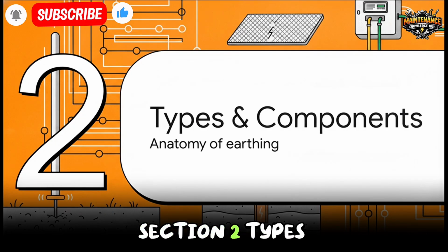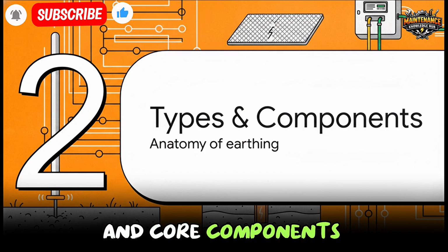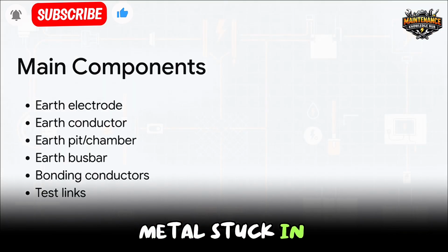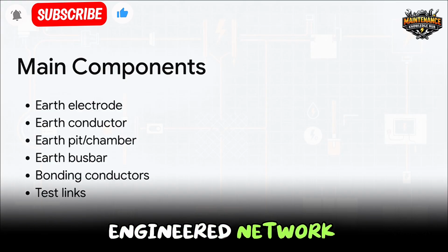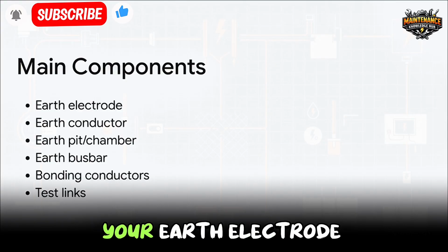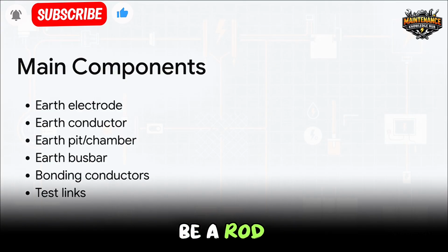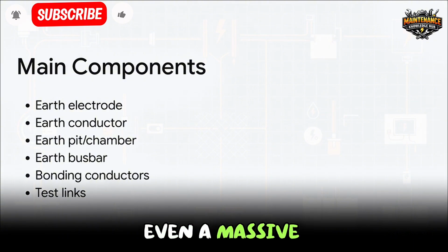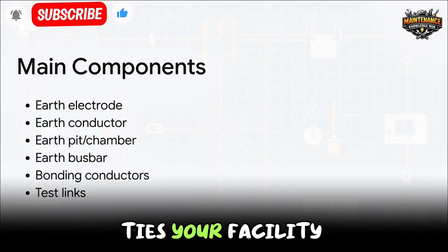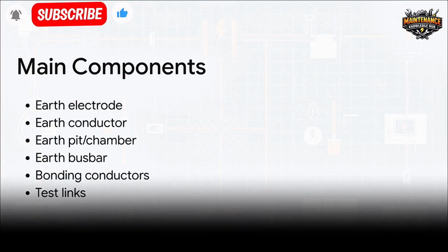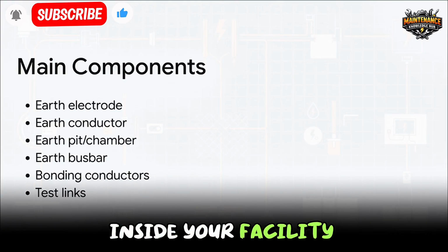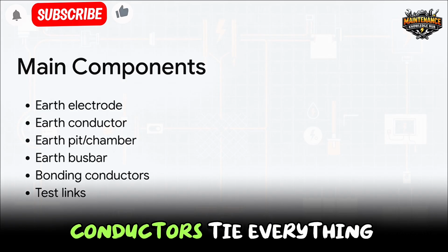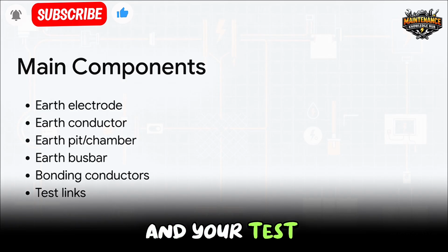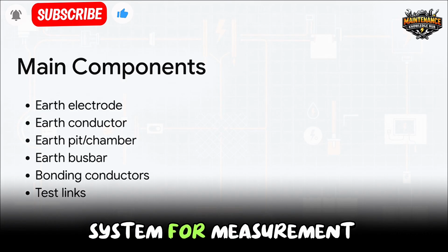Moving on to Section 2, types and core components. This isn't just a piece of metal stuck in the mud. It's a whole engineered network. Deep down in the soil is your earth electrode. And that can be a rod, a plate, a strip, or even a massive mat. The earth conductor ties your facility directly to that electrode, while the earth pit gives you physical access so you can actually test it. Inside your facility, the earth busbar and bonding conductors tie everything together, and your test links allow you to easily isolate the system for measurement.